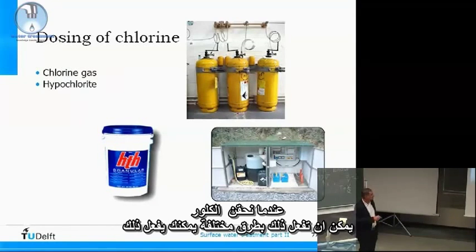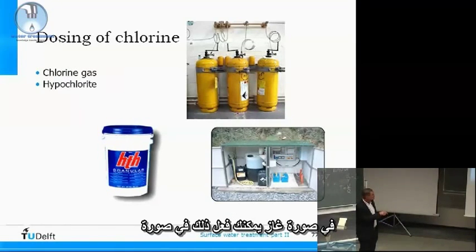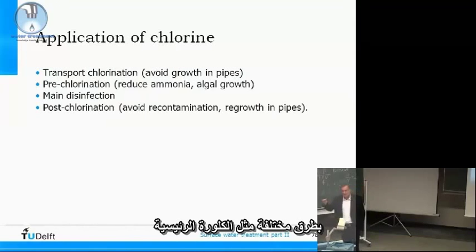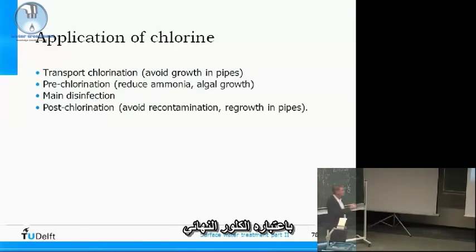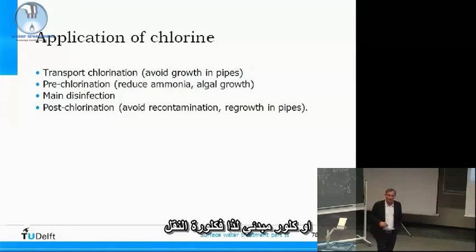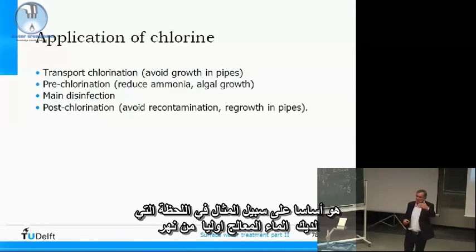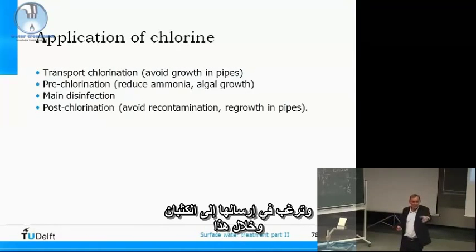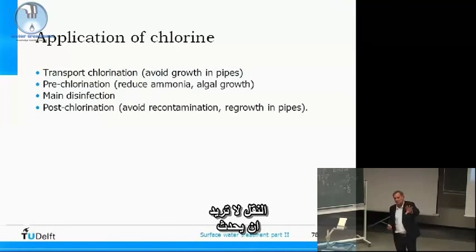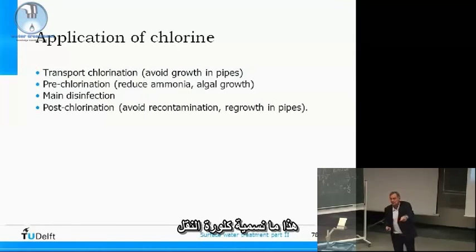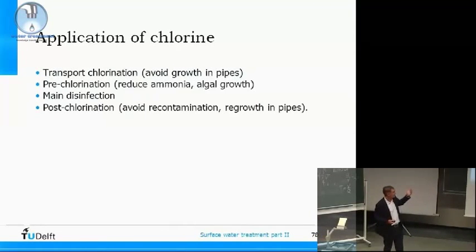When you dose chlorine, you can do it in different ways — as a gas or as a powder. You can apply it in different ways: as a main chlorination, as a post-chlorination, and sometimes also as a transport chlorination or pre-chlorination. Transport chlorination is mainly used when you have pretreated water from, for example, the river Rhine and you want to send it to the dunes. During that transport, you don't want regrowth in your transport main, so you dose a little bit of chlorine.